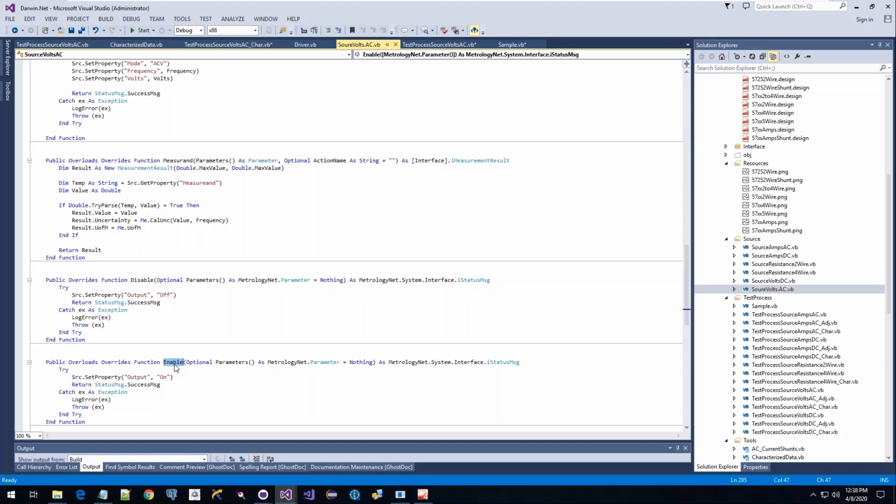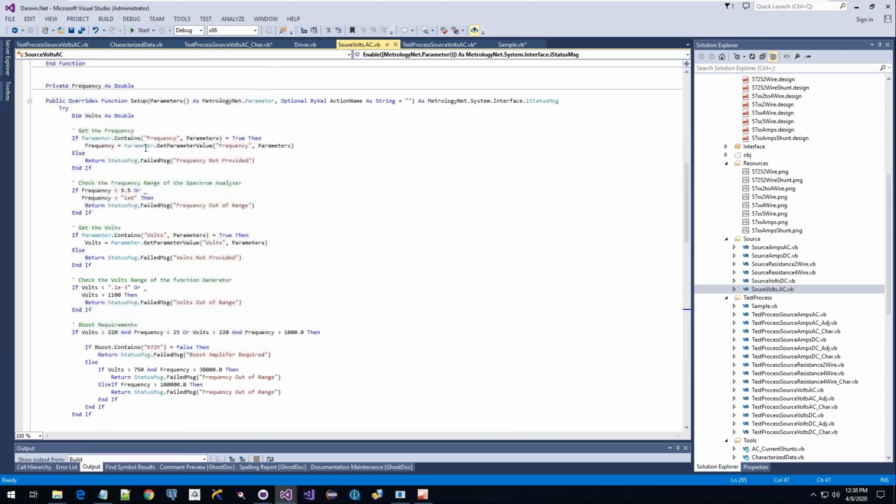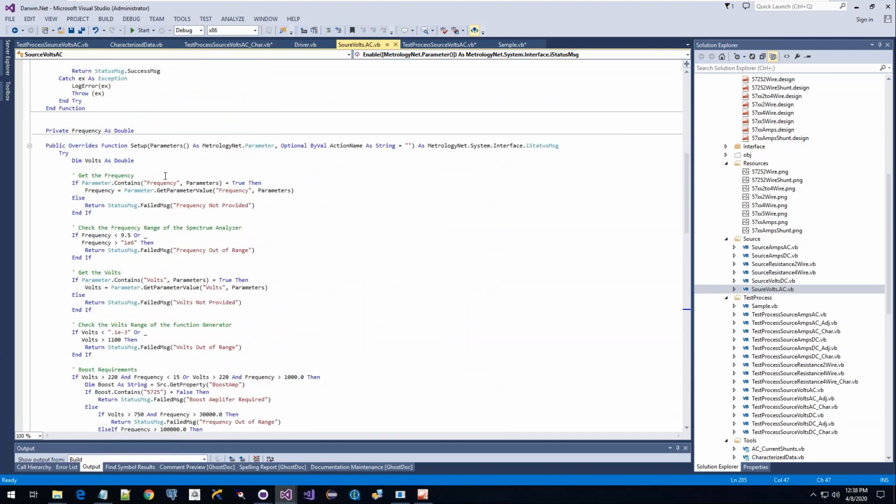So we're not talking to it in terms of its commands that are going out. We're talking to it in terms of the functionality that we want out of this. And the functionality gets wrapped up into the simple interface of set yourself up, turn your output on, turn your output off. And that allows us to take something like a 5500 with our measurement process and make that interchangeable with something like a signal generator, talking to it in this simplified interface.